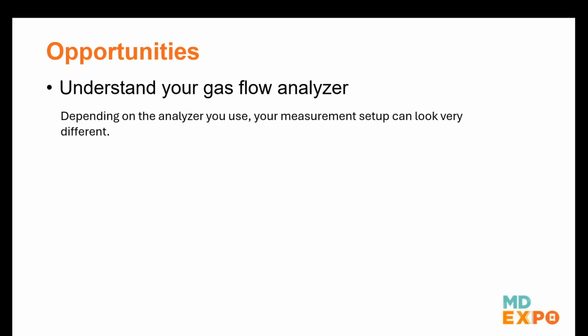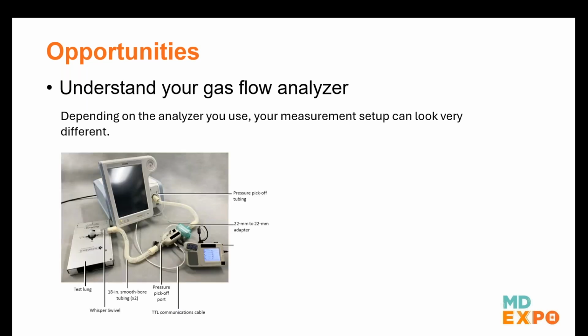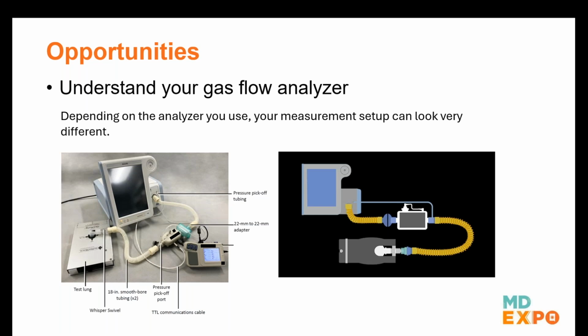Depending upon the analyzer that you use, you can have very different setups and still measure the same parameters. Case in point, our first photo that we had here, right? It's a photo with an analyzer. It looks fairly straightforward, fairly complex actually. And so if we substitute a different analyzer, we might have a much simpler setup. Still can measure all the same things, just with a different analyzer. Either way, you need to know what your analyzer is capable of and what are all the components of the analyzer. Some have a lot of components, some have very few.